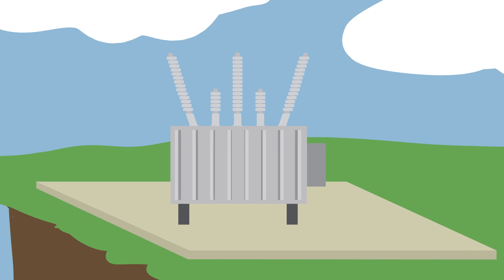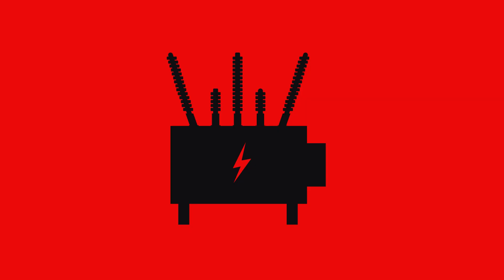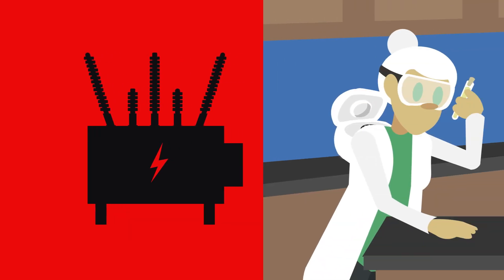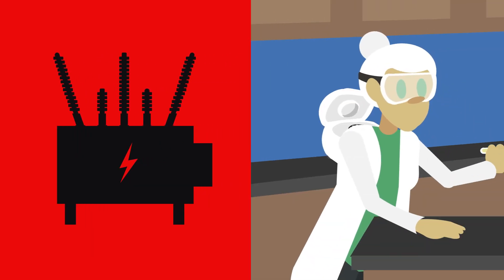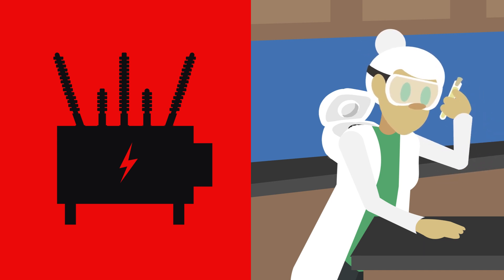When bushings are energized at line potential and operating at higher temperatures, the stresses in the bushing are increased. This makes the online monitor more sensitive and may result in cases where the online and offline values do not match.